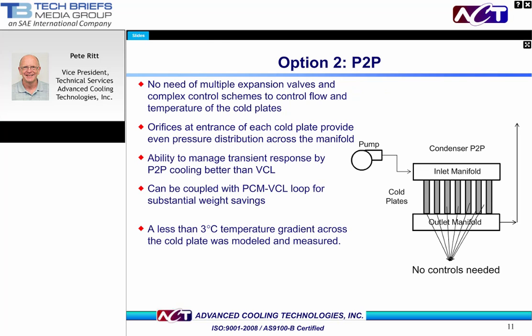Let's take a look at some of the advantages the pump two-phase system offers in this application. There is no need for multiple expansion valves required in the vapor compression loop. That can be handled by a single manifold. Orifices at the end of each of the cold plates provide even pressure distribution across the manifold and can be used to self-regulate the flow across each of the individual cold plates. This approach enables the transient response across the different cold plates to be more efficiently addressed. And as we have seen, it can be coupled with other thermal management systems in a space-efficient way. Finally, the temperature uniformity across these cold plates is quite good, as we'll see on the following page. Both prediction capability and actual results are impressive.